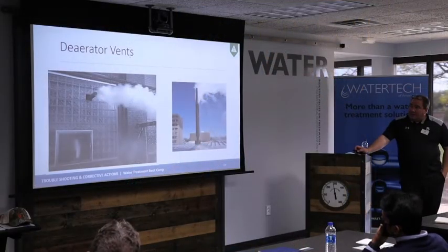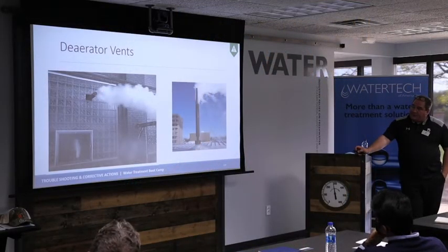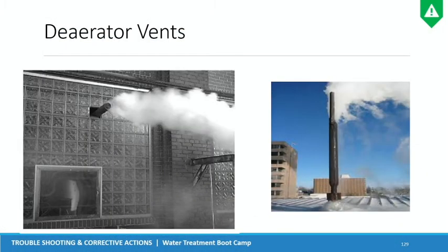So here we have a plume coming out. Now, I would say pay attention to this closer plume, not the fact that it comes out here. But here we could have a potential situation where maybe you don't have enough pressure coming out of that plume. Even though it is horizontal, typically you see them vertical, you really don't have a driving force, where you would say that the diameter of this pipe is about the same diameter as that, 18 inches or so out from here. The other reason to have it that way is that if you have enough steam coming out of there, you're not corroding that pipe, because you have exit velocities that are not allowing condensate to form. So hopefully it's not allowing moisture to condense or steam to condense inside the tube.